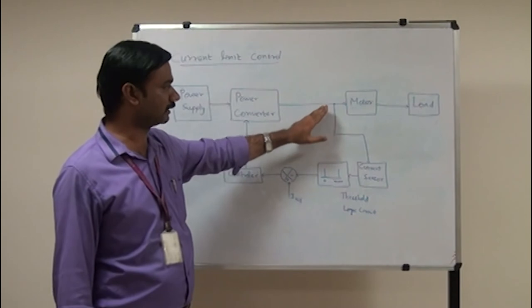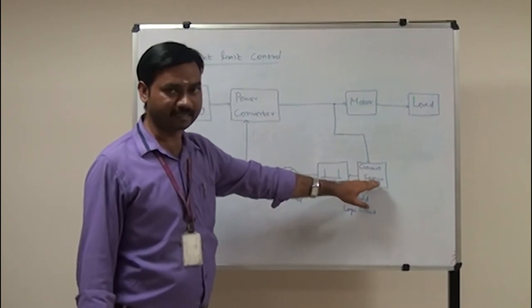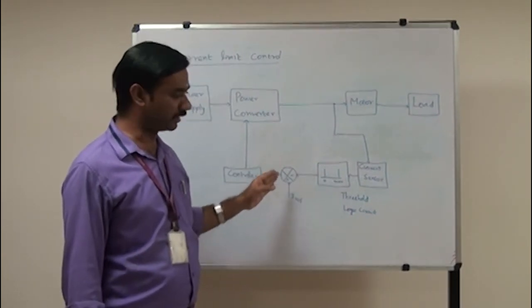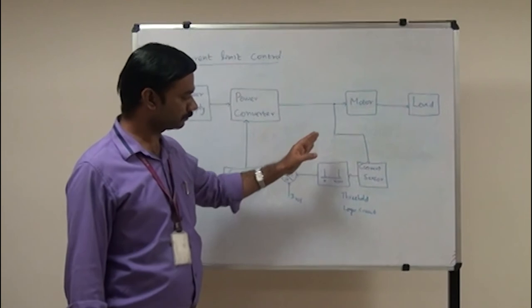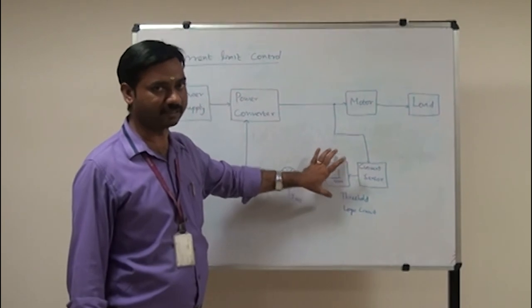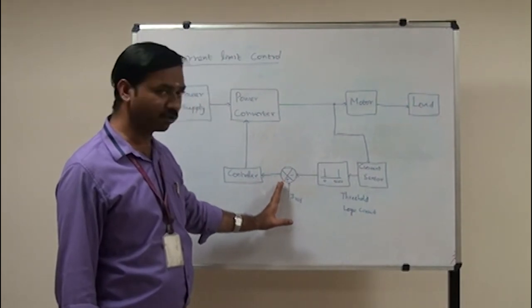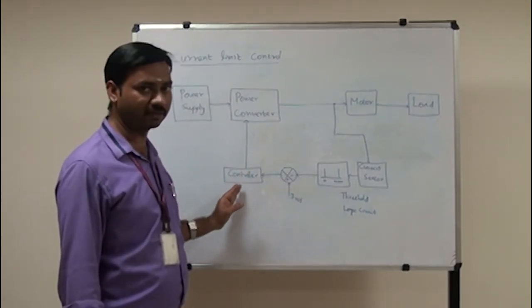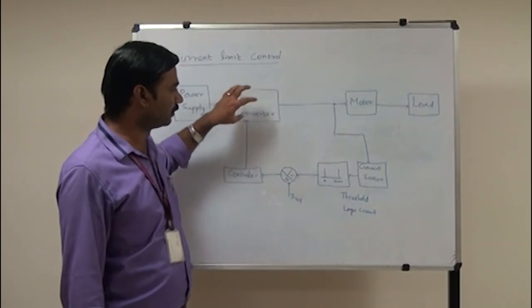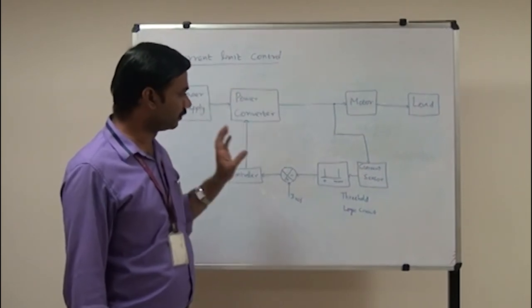To implement current limit control, we add a current sensor at the motor output. The current sensor signal is given to the comparator through a threshold logic circuit, where we set the maximum allowable current limit. The comparator produces an error signal, which is given to the controller. The controller then controls the power converter — specifically, it controls the on/off state of the switches in the power converter.